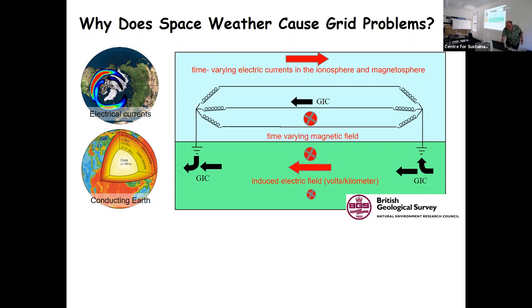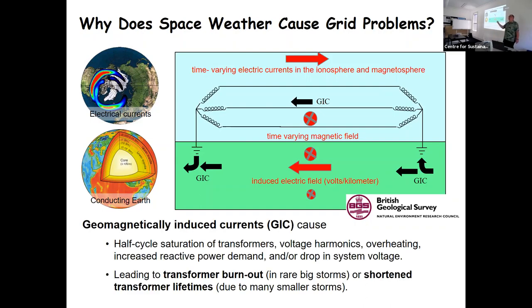We'll have a voltage difference between the earthing points of the network, and that causes currents to flow up through one earthing point, through the power line, and down through other earthing points. The issue is that in a functioning electrical power network, those earthing points are the main grid power transformers. So currents flow through those transformers, and they're not meant to be there. The transformers aren't designed to have those currents present, and they don't like them. They lead to things like half-cycle saturation, which produces harmonics and can cause instability in the network.